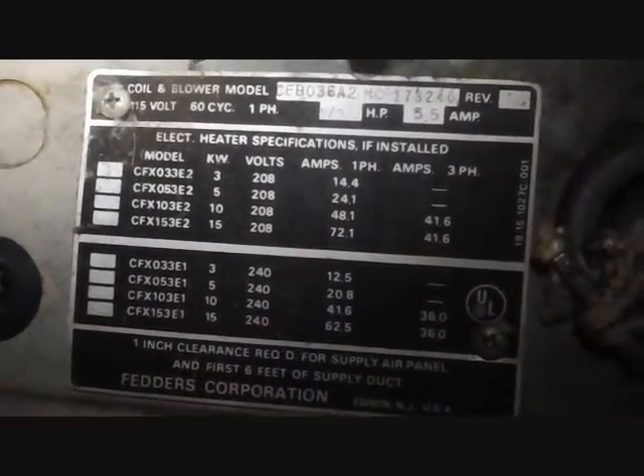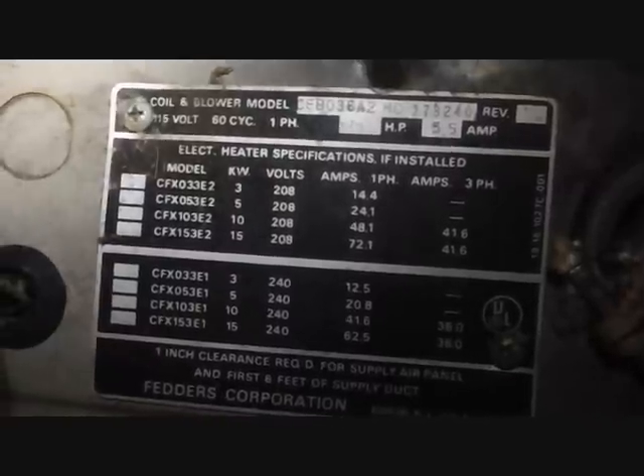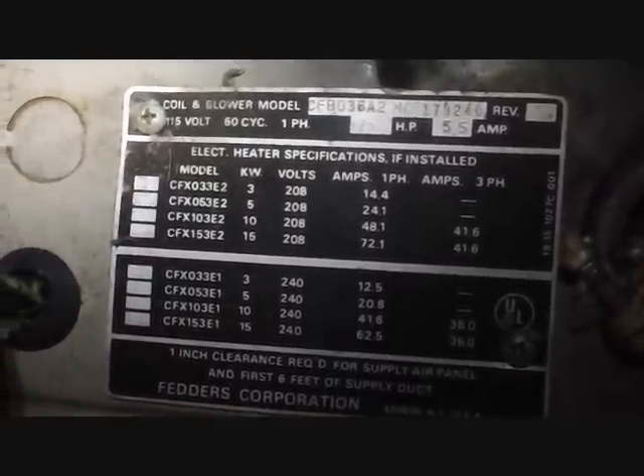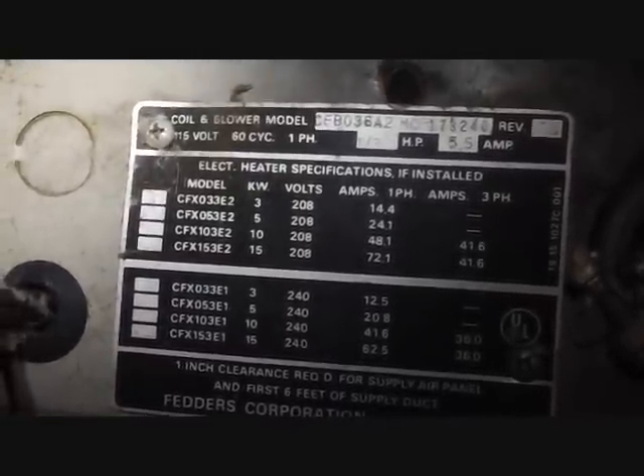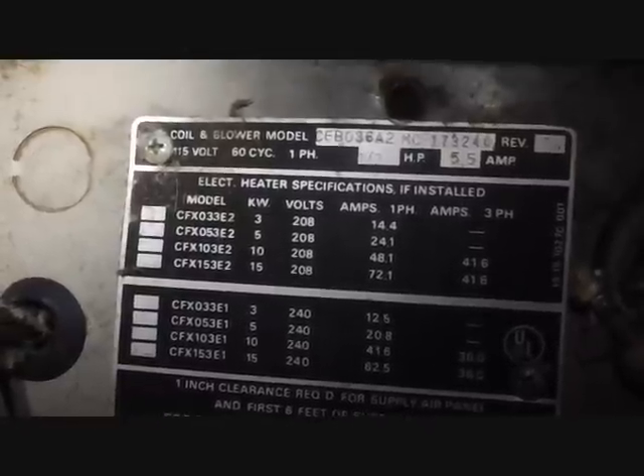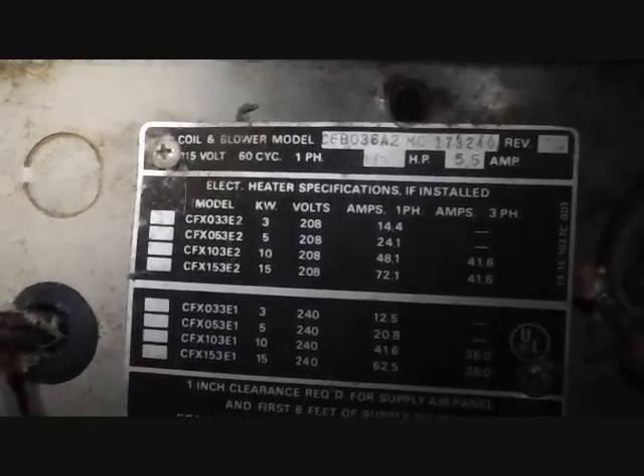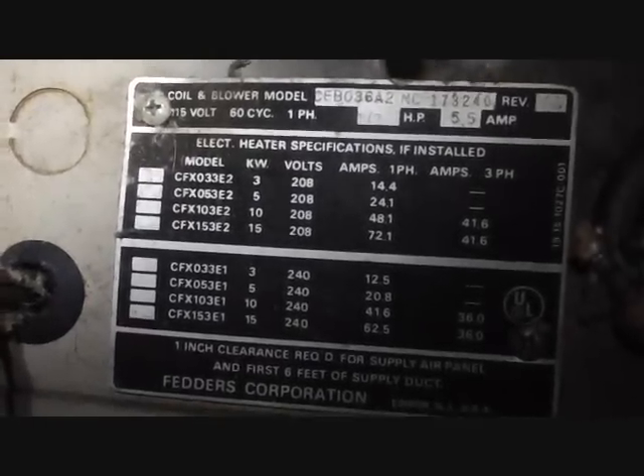Here's our old fan coil we're taking out of the top. It's very old — about 30 years old — probably about the same age as the package unit that we ripped out downstairs. Heat strips are in it. I'm not quite sure what kilowatt it was, but I'm assuming it was probably the CFX 15 because they had two circuits running to it. So that's what we've taken out upstairs.